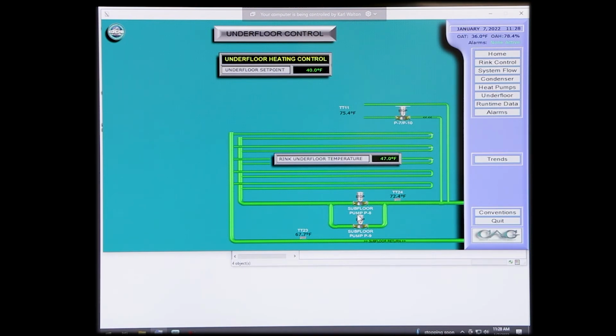That's where you'll see, again, we talked about the algorithms of how we run these underfloor pumps and what we look at and how we cycle so that we make sure that we keep that glycol loop temperature warm. We want this TT11. We want this 100 degrees. We need it for your Zamboni hot water preheat. We don't want to kill that loop temperature when we start that underfloor pump. So we're going to cycle the pumps.